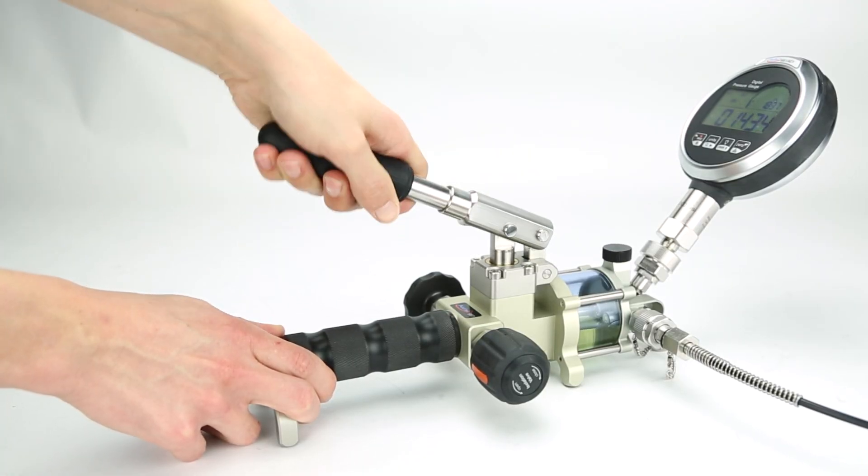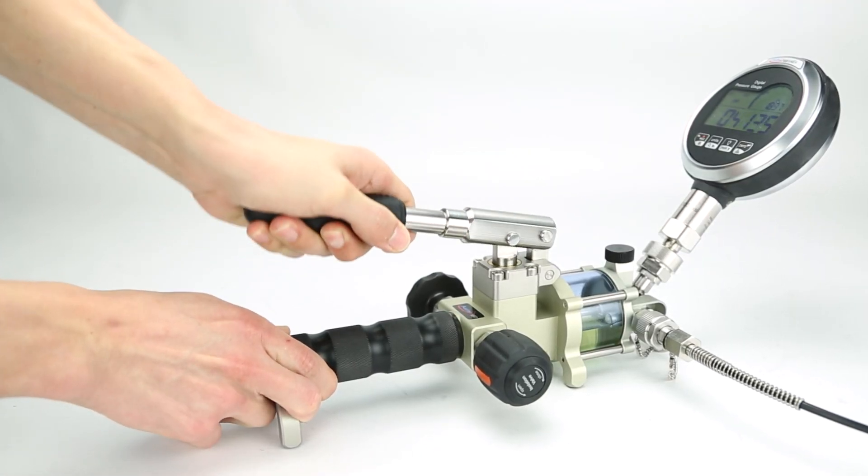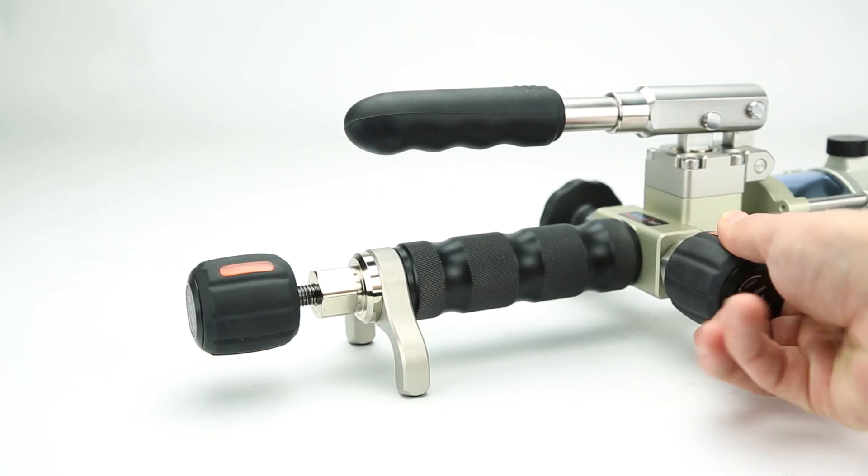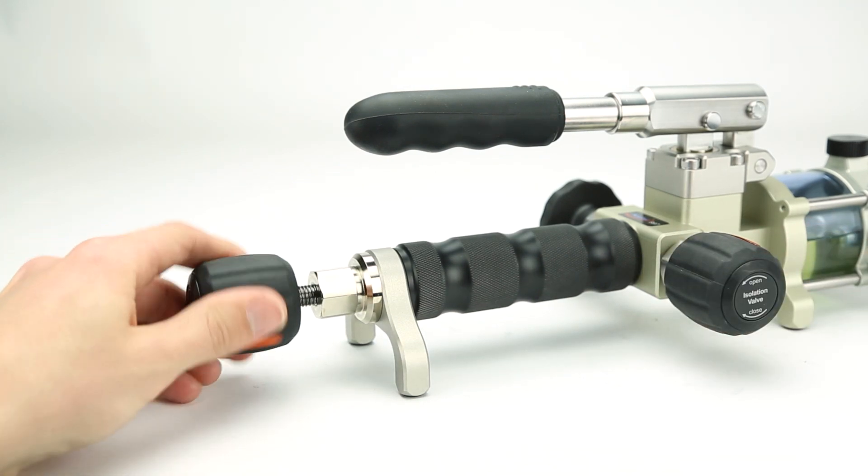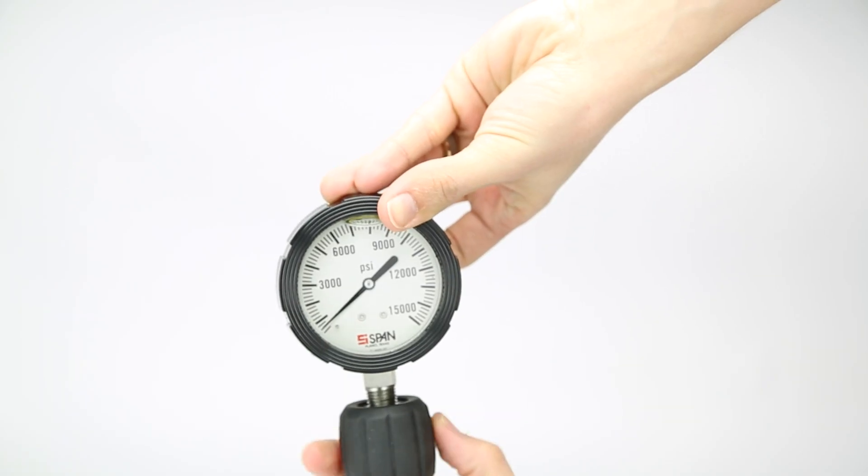When pressurizing, it will be difficult to go past 7,000 PSI using only the lever arm. At this point, close the isolation valve and generate the rest of the pressure using the fine adjust knob.